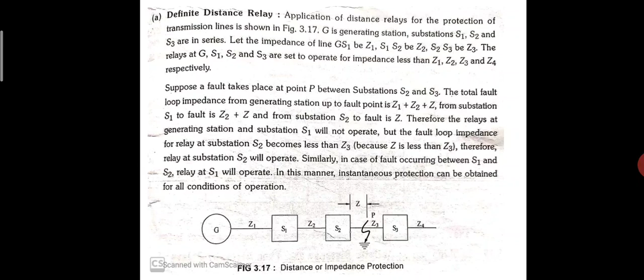So observe carefully. Suppose a fault takes place at point P between substation S2 and S3. The total fault loop from generating station up to fault point is Z1 plus Z2 plus Z. From substation S1 to fault is Z2 plus Z, and from substation S2 to fault is Z. Therefore, the relays at generating station and substation S1 will not operate, but the fault loop impedance for relay at substation S2 becomes less than Z3 because Z is less than Z3. Therefore, relay at substation S2 will operate. Similarly, in case of fault occurring between S1 and S2, relay at S1 will operate. In this manner, instantaneous protection can be obtained for all conditions of operation. This is the definite distance relay operation.